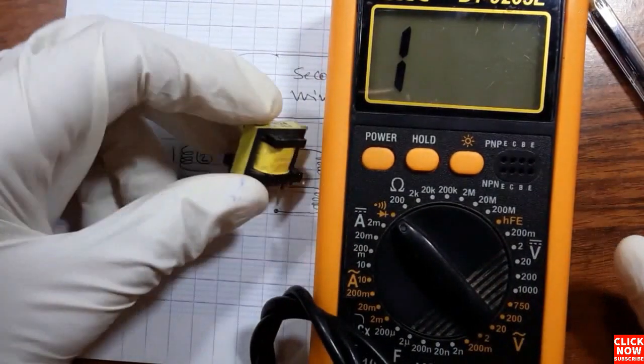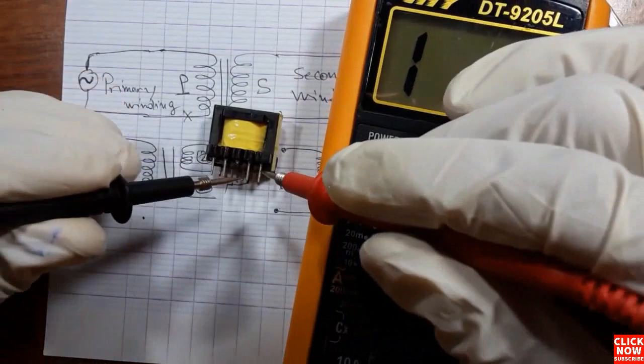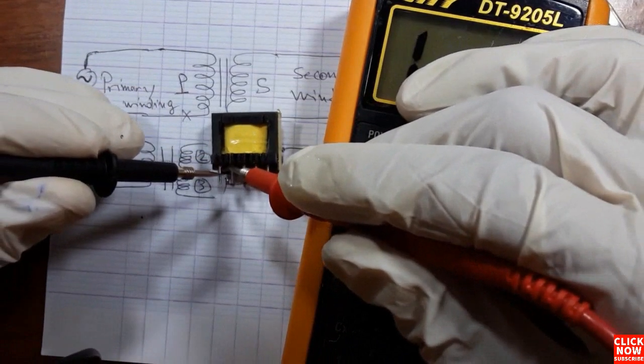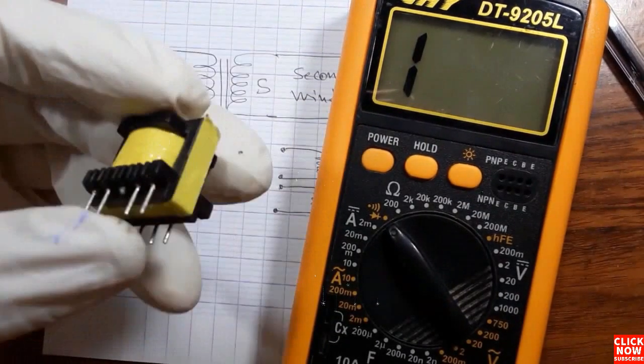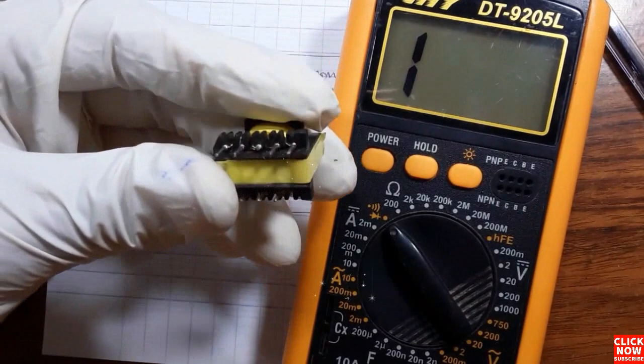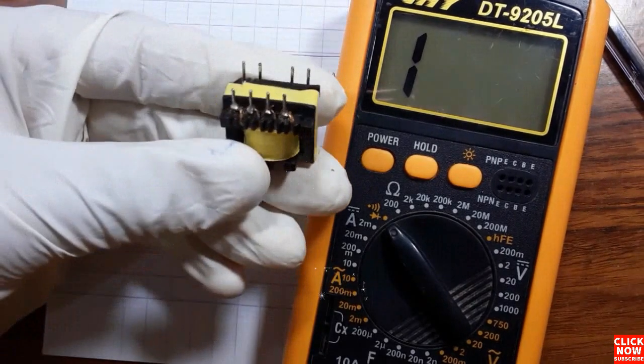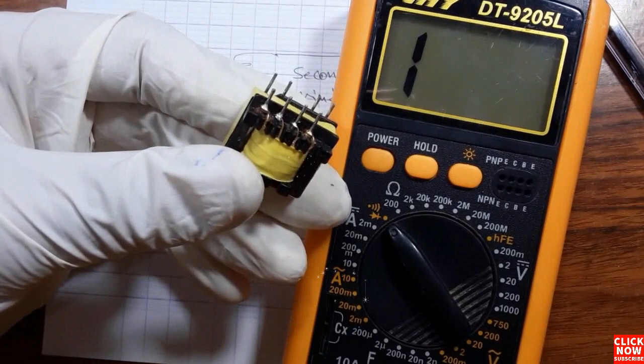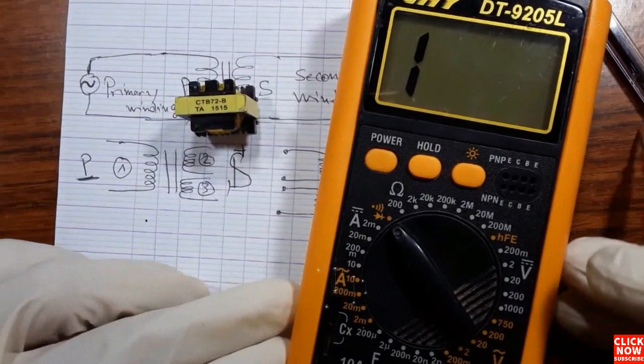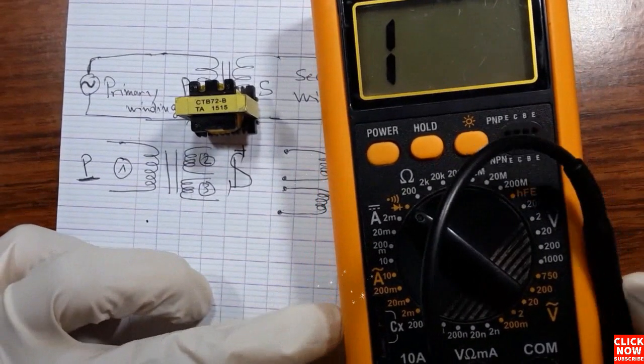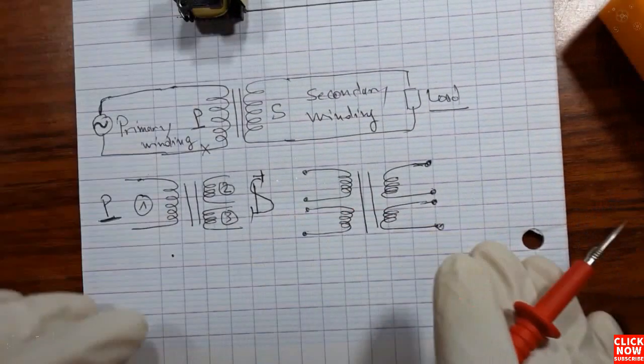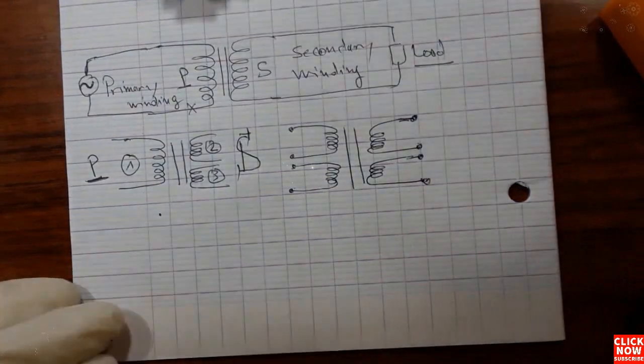The multimeter is a very important tool used to identify each inductor. Here we have one inductor and here the second inductor — basically this is the output, or the secondary winding. This transformer is a good, serviceable transformer. If you find any cut winding or don't hear any buzzer on any inductor, it means the transformer has failed.